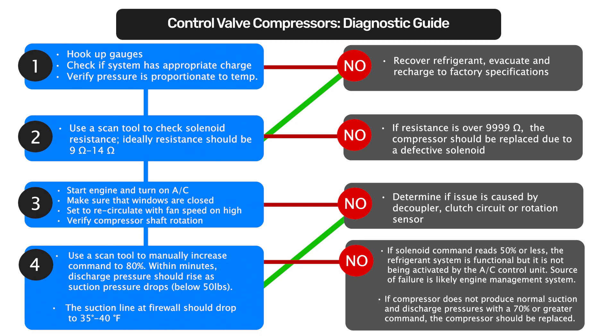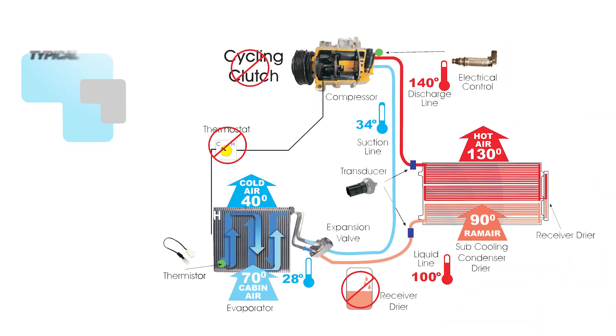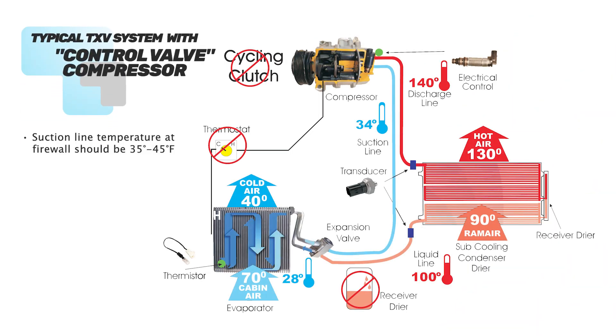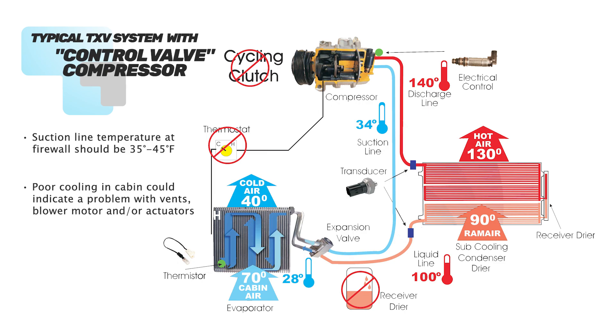If the compressor is unable to produce normal suction and discharge pressures with a 70 percent or greater command from the solenoid, the compressor should be replaced. You should also monitor the suction line temperature at the firewall — 35 to 45 degrees Fahrenheit indicates a normal refrigerant system.